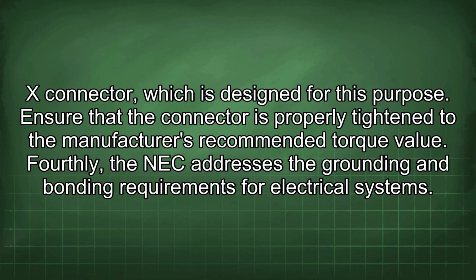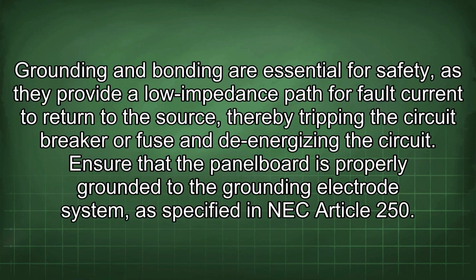Fourthly, the NEC addresses the grounding and bonding requirements for electrical systems. Grounding and bonding are essential for safety, as they provide a low impedance path for fault current to return to the source, thereby tripping the circuit breaker or fuse and de-energizing the circuit. Ensure that the panel board is properly grounded to the grounding electrode system, as specified in NEC Article 250.